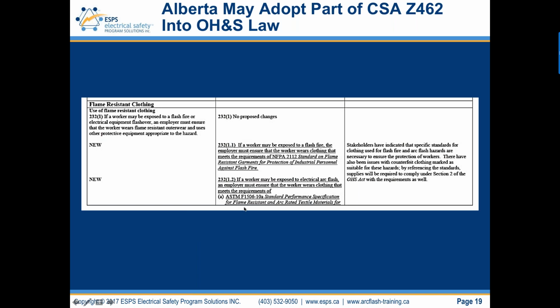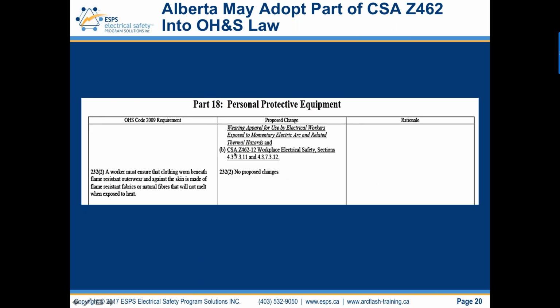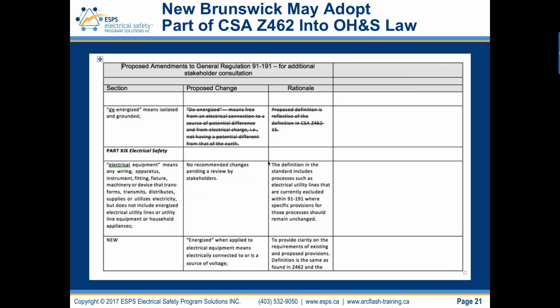Then they're going to adopt ASTM F1506 into law, and two clauses in Z462 into law that relate to defining arc flash PPE with an arc thermal performance value or a break open threshold energy. That's just two clauses, but it sets off that you may want to do a little more effort in reviewing the rest of the document. In New Brunswick, out in Eastern Canada, they have been for the last year and a half, maybe 2 years, updating their electrical safety content and their OH&S regulations, potentially adopting all of Z462. It says part, but they've also considered adopting all of it. If they do go ahead, I believe it would probably be part of Z462 that would be referenced formally. So that'll be in the province of New Brunswick out in Eastern Canada.